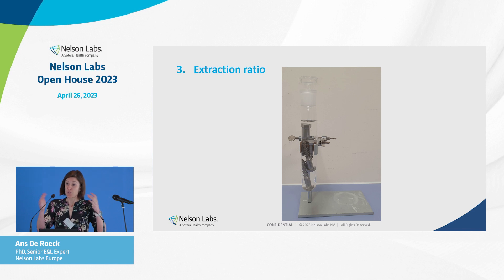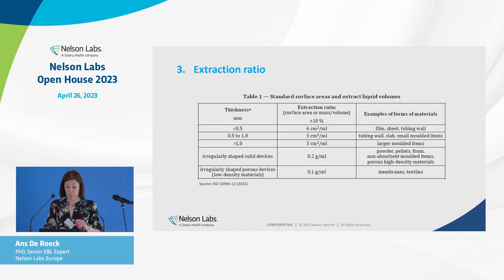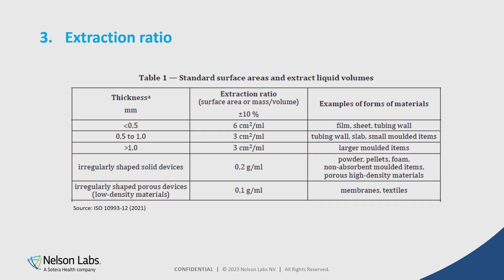Now we know which solvents to add — but how much? What is the extraction ratio? Part 18 doesn't say anything about this, so we often use Part 12. Depending on the thickness of the device, we often use 3 or 6 cm² per mL. When it's difficult to calculate the surface area, it's also possible to use a weight-based ratio.